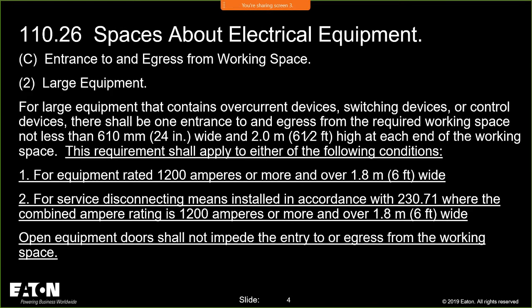For the working space, you need an entrance at each end when you have equipment rated 1200 amps or more, or when the service disconnecting means add up to 1200 amps. In the past, we'd use a 6-disconnect rule to keep everything below 1200 amps, which kept us out of adding that extra door, out of GFPE, and out of arc reduction requirements in 240.87 and 240.67. That's not going to be available anymore.